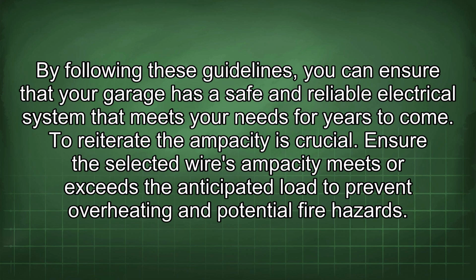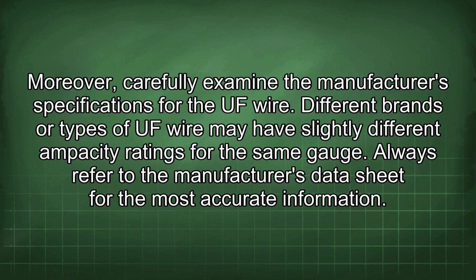To reiterate, the ampacity is crucial. Ensure the selected wire's ampacity meets or exceeds the anticipated load to prevent overheating and potential fire hazards. Moreover, carefully examine the manufacturer's specifications for the UF wire. Different brands or types of UF wire may have slightly different ampacity ratings for the same gauge. Always refer to the manufacturer's datasheet for the most accurate information.